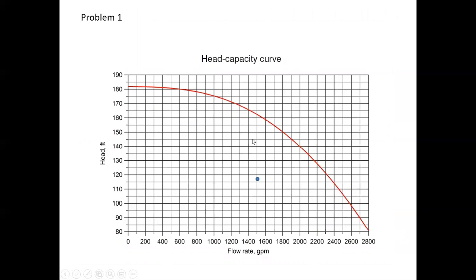It doesn't look like the one published by the manufacturer, but anyway, it's a pump curve. And of course, we're not showing it all the way through 0 on the feet of head axis, just to blow it up a little bit. So we put in 1,500 at about 117 feet, and we go, oh my, that's nowhere close to the pump curve. Well, what that tells me is my initial guess of 1,500 GPM is wrong. For this part, A1, we're assuming that the pump operates on the pump curve. So we have to go back.